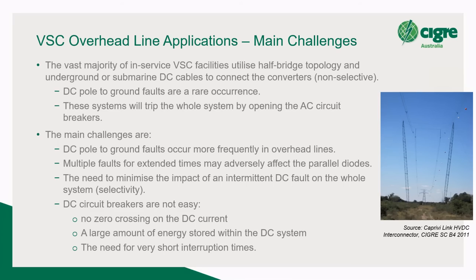So they assume that if you're going to get a fault on an underground or a submarine cable, it's going to be a permanent fault. It's not an intermittent fault. And therefore, you may as well just open the AC circuit breaker, right? You're not going to try and restart that. So that's pretty much the bulk of the VSC at the moment. But of course, with new opportunities and new applications, everyone now wants to be able to use VSC on overhead lines. The difference is that DC overhead lines, or any overhead line, is susceptible to intermittent faults. So you can no longer assume, well, I'm going to open the circuit breakers every time I get a fault, because you'll have a pretty unreliable interconnector if you did that.